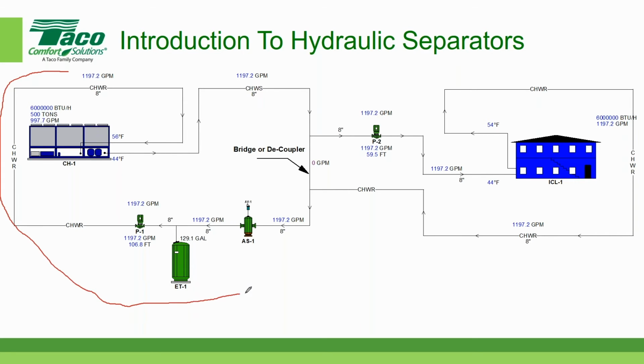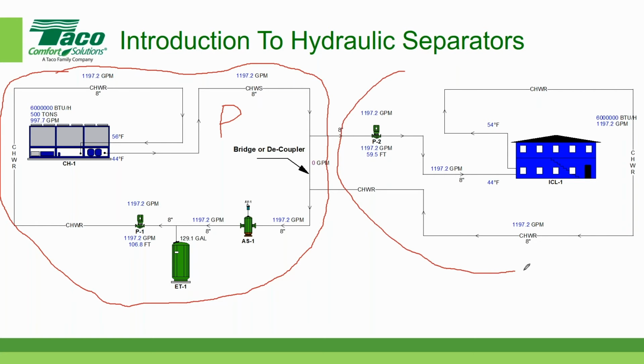We have this diagram on the left side, and we're going to call this left side of the screen the primary loop. And on the right side of the screen, we're going to call this the secondary loop. I'm using the letter P for primary and the letter S for secondary. Generally speaking, most people will refer to the primary loop as the source, either the chiller, the boiler, cooling tower, something like that. And the secondary loop will be the load side of the system. Sometimes people interchange these back and forth, but for our purpose today, we're going to stick with the most common terminology for primary, secondary loop.